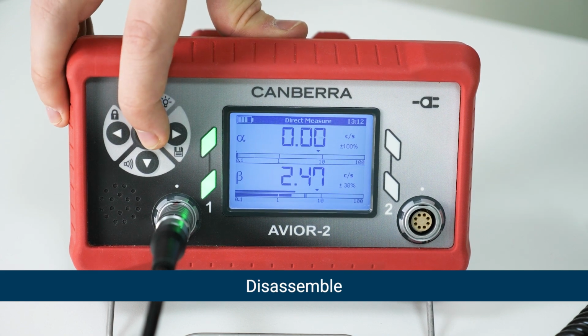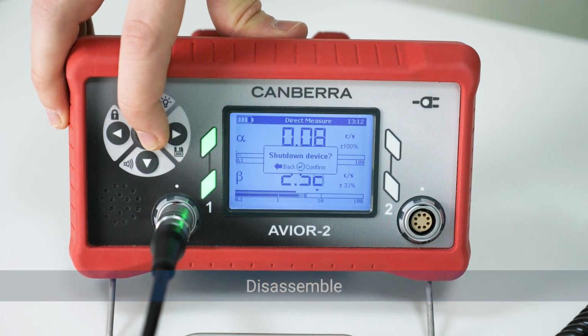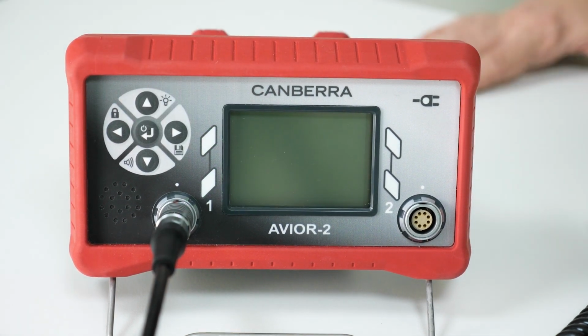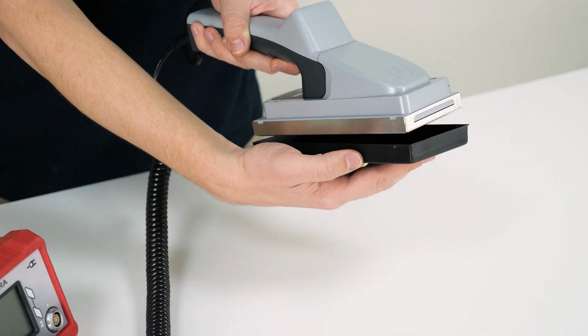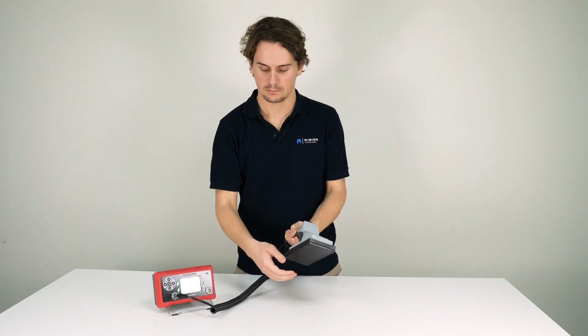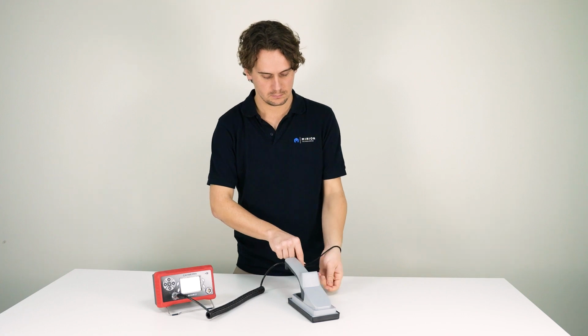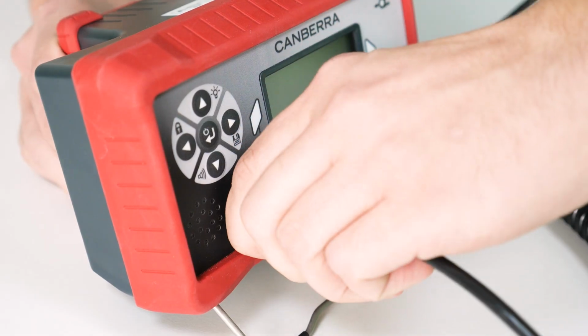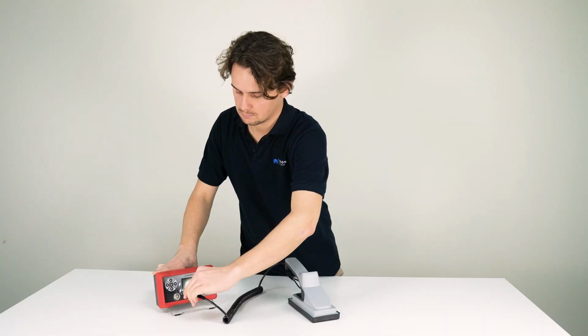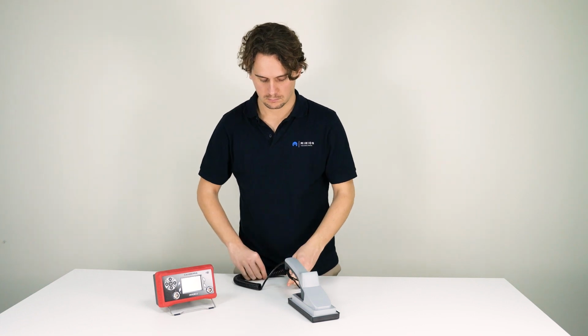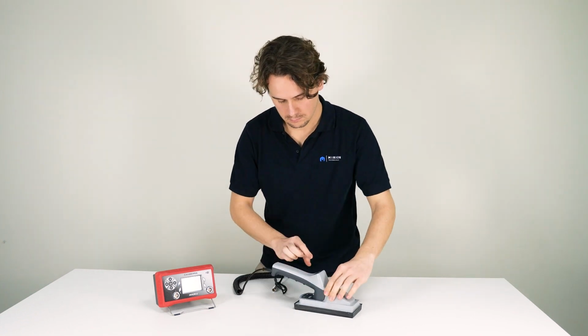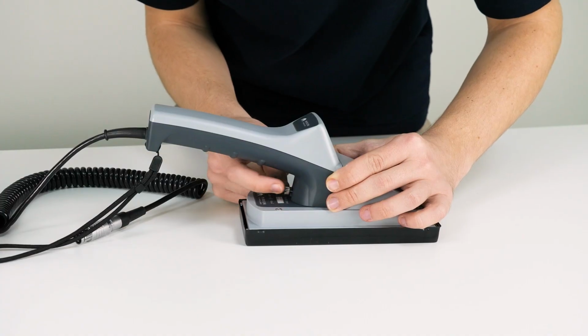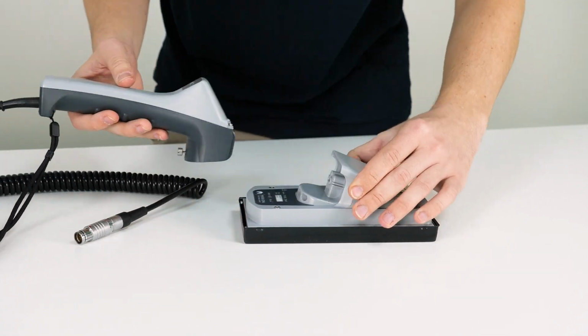After use, turn off the AVIOR-2. Place the protective cover back onto the AB-100. Unscrew and pull the connector off to disconnect the AVIOR-2. Unscrew the screw on the CSP-C handle. Disconnect the handle from the AB-100.